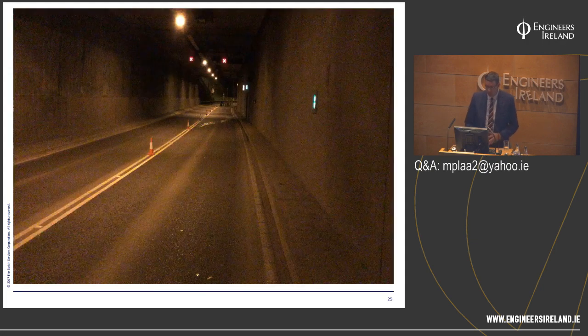And one of the other things I've done this year, I've tested a major road tunnel in the northeast of England. And what I did, we went there with a colleague at midnight and tested 45 metres of the water mist system. Actually got them to fully discharge. We closed the road tunnel and discharged the water mist system to make sure it was fit for purpose. In this case, everything worked absolutely spot on, just as is intended. So we do have some good news stories, but it gives us confidence as engineers that we've actually proven the system is fit for purpose in anger.